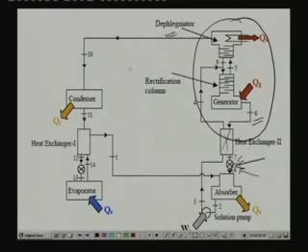In the dephlegmator, the refrigerant vapor rejects some of the heat to a heat sink. That means some heat rejection takes place in the dephlegmator. That heat rejection is given by QD, and due to this heat rejection, some of the solution condenses in the dephlegmator, that is known as reflux. So, I will explain this while explaining the rectifying column.